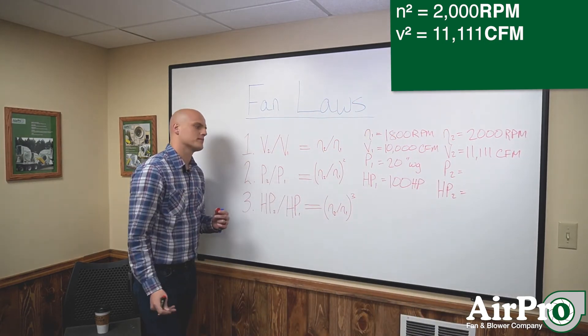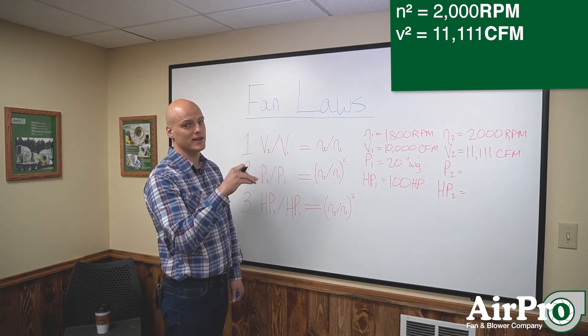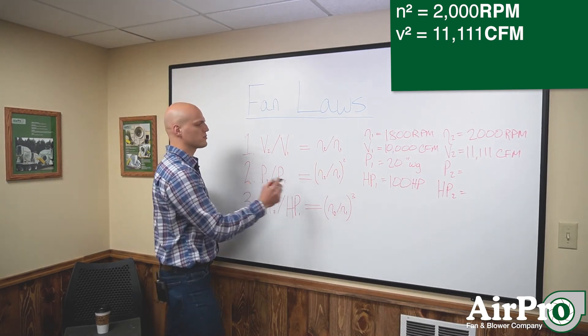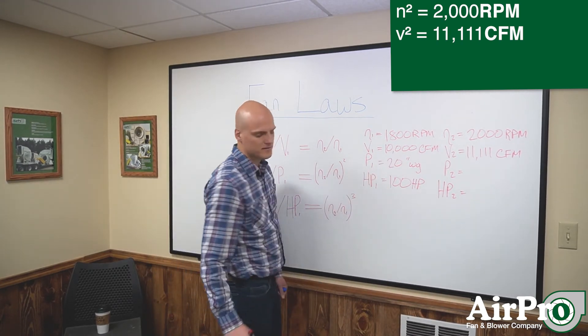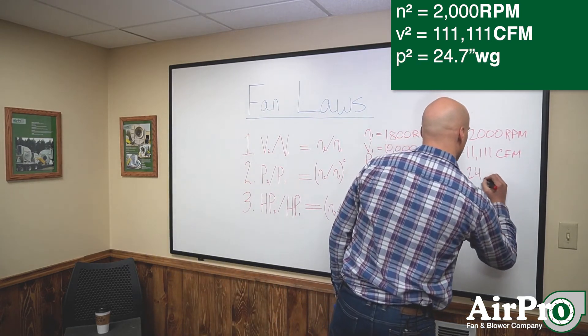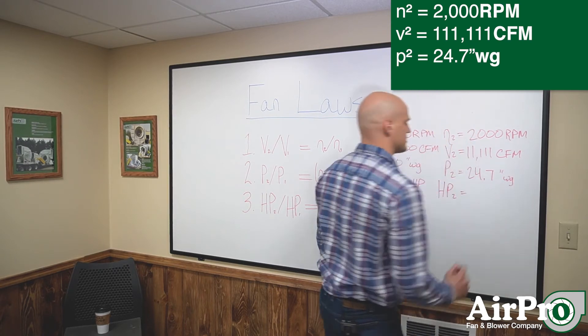Pressure. We're going to gain a factor of 2,000 divided by 1,800 squared and then multiply that by 20. And we get 24.7 inches of water.